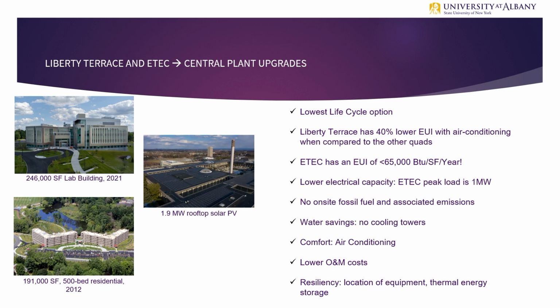Comfort-wise, air conditioning is now an extra you get free from this system. In fact, I want to air condition, because I want to use that as a resource for heat. So perfect, I can air condition. There's lower O&M cost, and really resiliency: most of the asset, the bore field, is buried underground with a 50 to 100 year life. All the other heat pump equipment is inside the building, so I don't have equipment outside subject to weather. From a resiliency point, it works out.